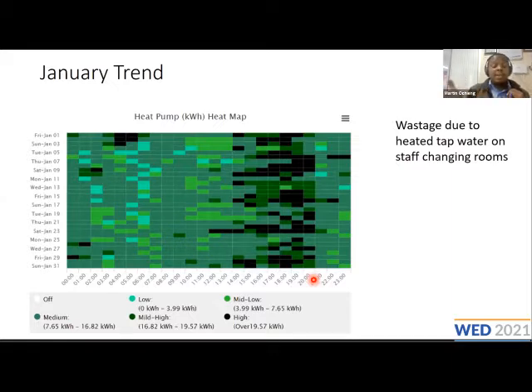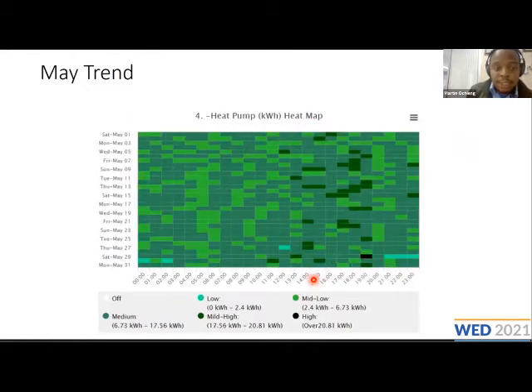So from this, we were able to identify that the heat pump actually consumes a little more than it should in the staff changing rooms, specifically on the taps, where it isn't really necessary. So on further discussion with the team, we identified a possibility of reducing energy consumption by removing the hot water element from the staff changing room taps. And this was the heat map for the January trend, as you can see. And on the latest heat map, for last month, there's been a significant change in how the patterns behave in that section. That means the consumption in the staff changing rooms has reduced significantly.